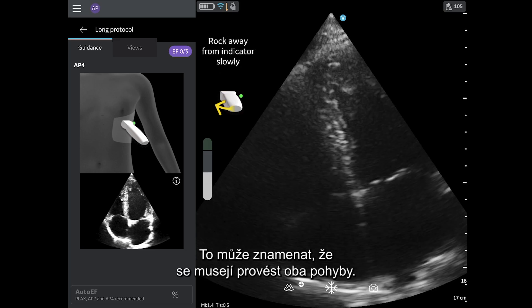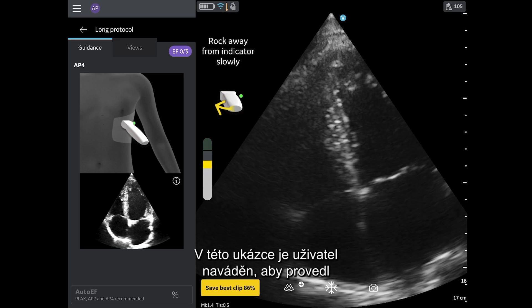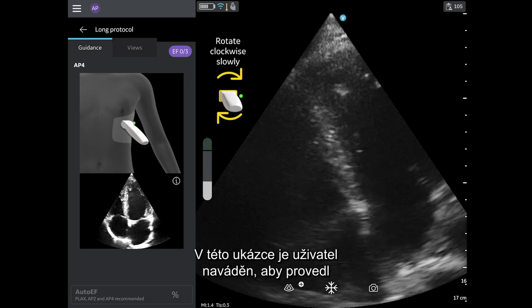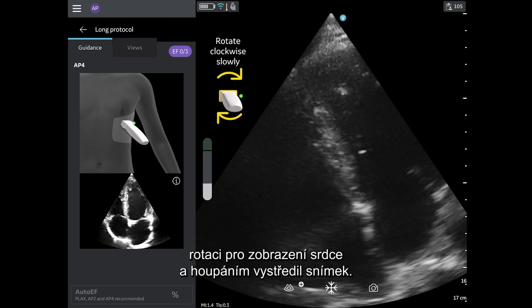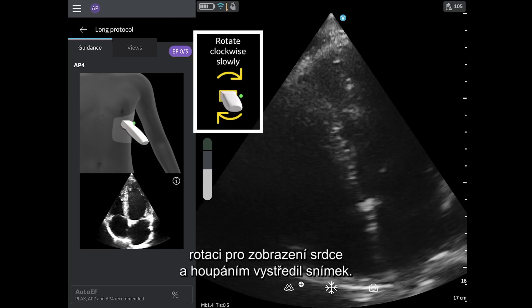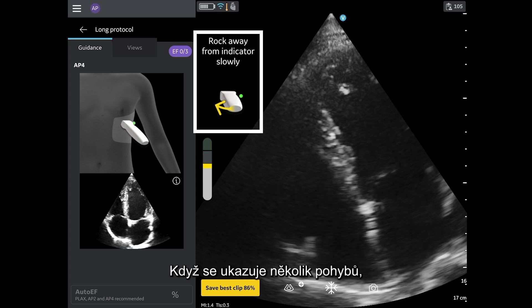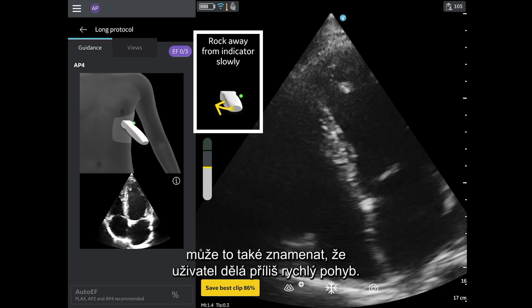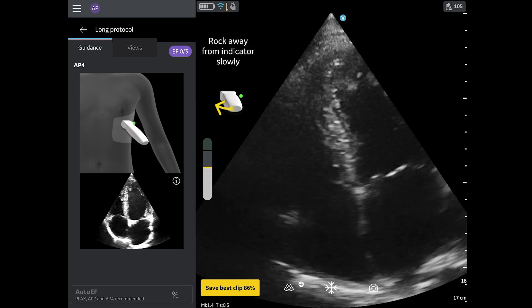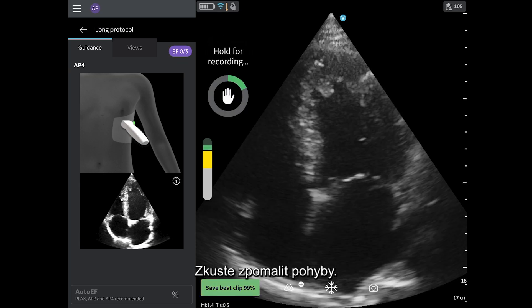This may mean that both movements need to occur. In this example, the guidance is directing the user to both rotate to see the heart, and rock to center the image. Having multiple movements appear may also mean the user is moving too quickly. Try to slow down your movements.